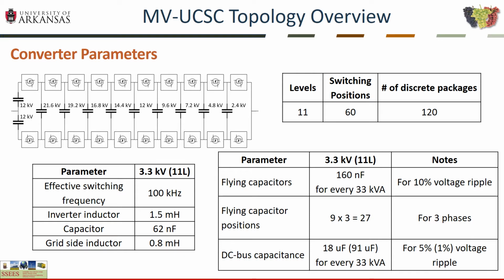There you have the LCL filter specified below. On the other table on the right hand side, you have the flying capacitors, 160 nanofarad for every 33 kVA if we want to get a 10% voltage ripple. The flying capacitor positions are 27, 9 per phase times 3, and the DC bus capacitance is 18 microfarad if we want to get 5% voltage ripple, or 91 microfarad per 33 kVA if we want to get 1% voltage ripple.